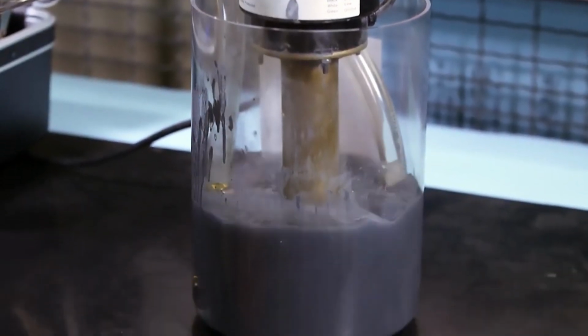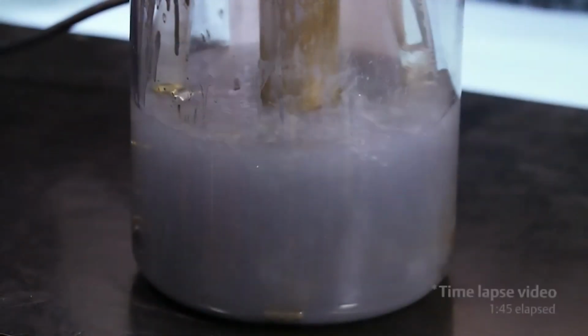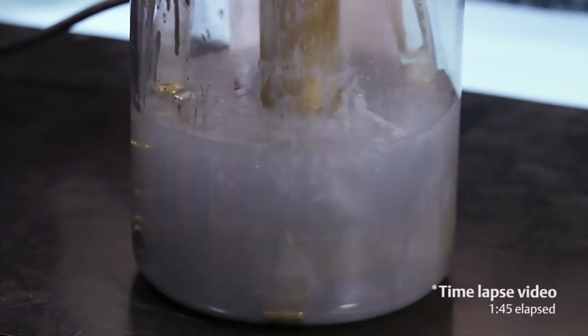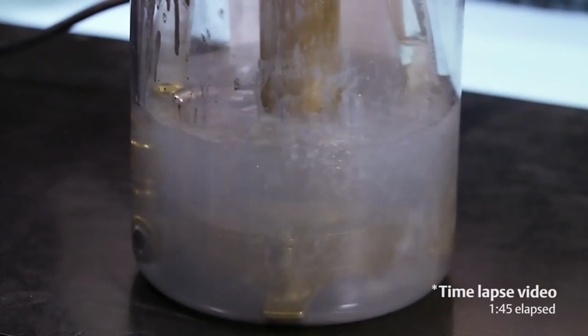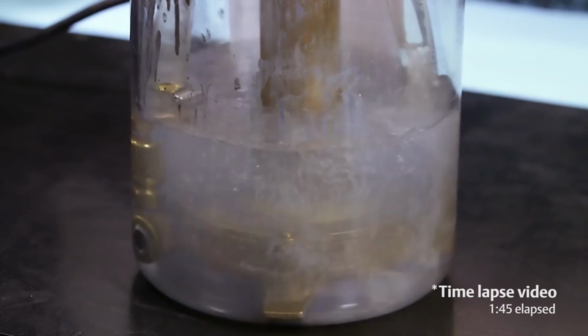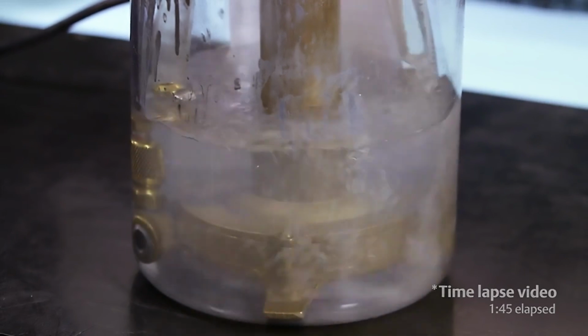Now we add another 5 grams of contaminant. You'll see how quickly the Copeland EK cleans up the system. In about 1 minute and 45 seconds, the EK cleans up not only the contaminant left in the system by the competitor's filter dryer, but also the grit we just added.